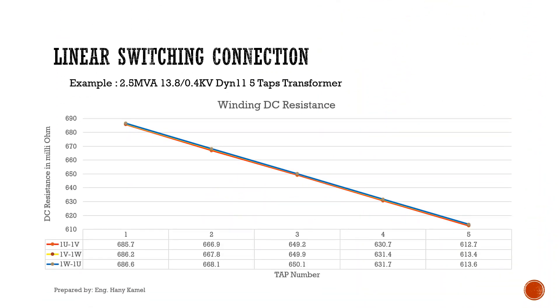For DC winding resistance, we have an example: a 2.5 MVA transformer, 13.8 over 0.4 kV, with vector group DYN11 and 5 taps. The DC winding resistance is as shown in the curve. Tap number 1 has the highest value and tap number 5 has the lowest value.